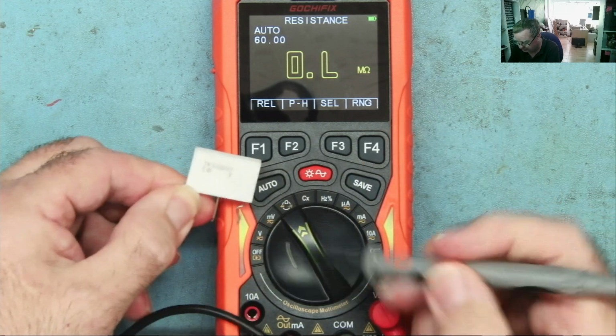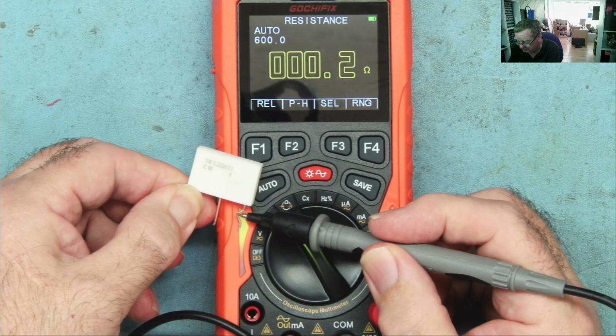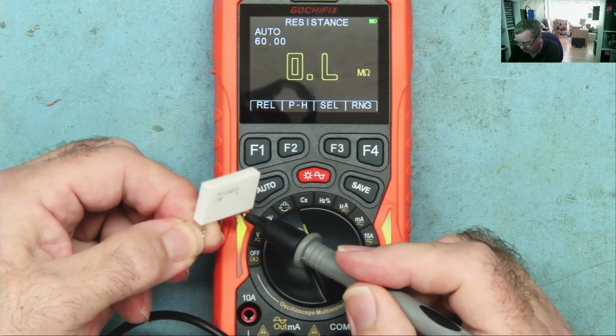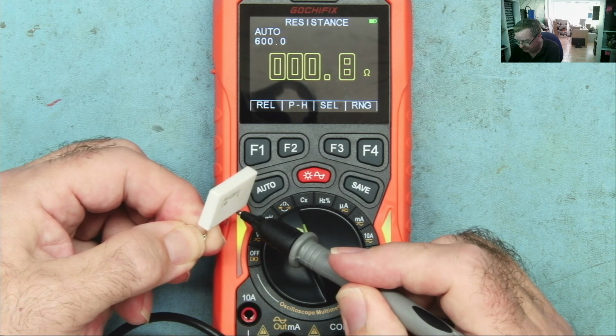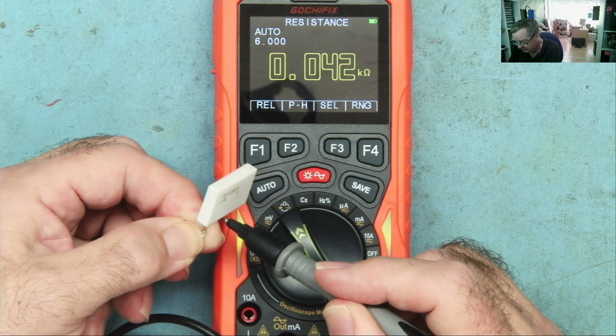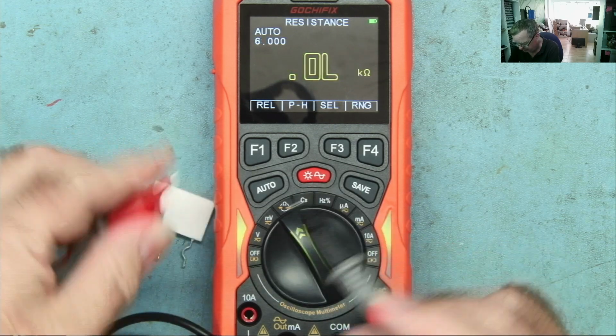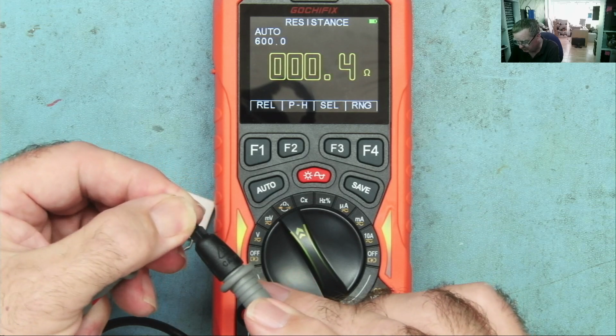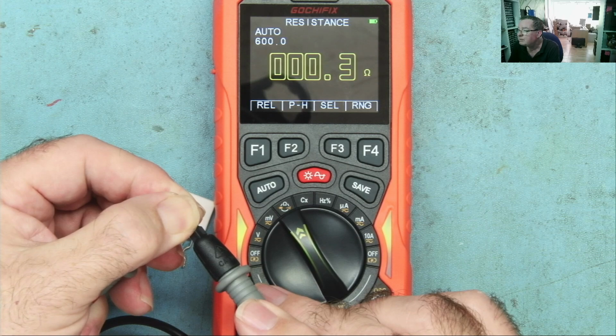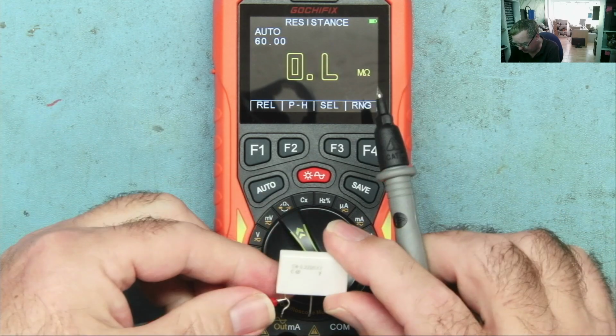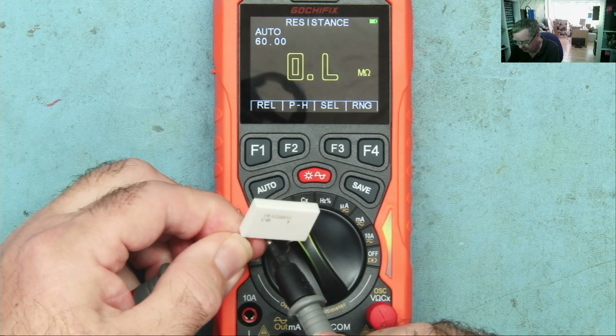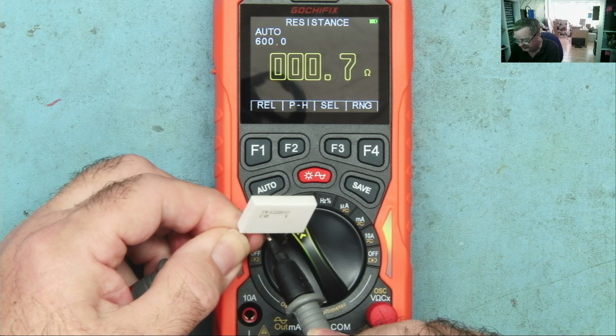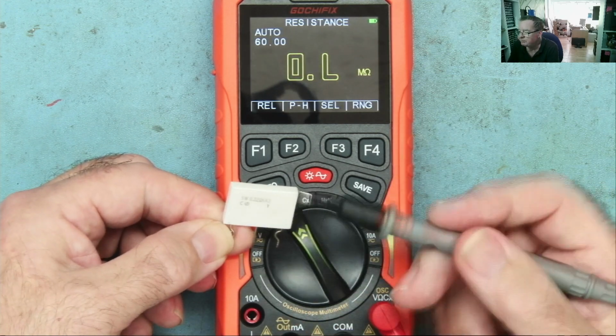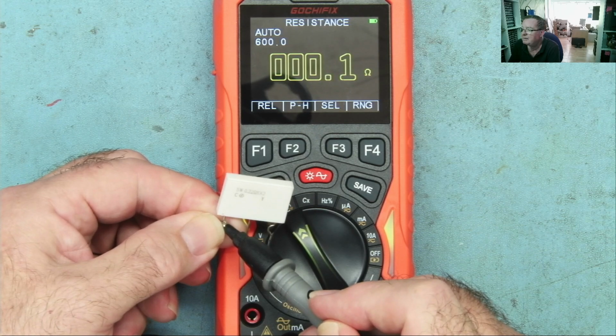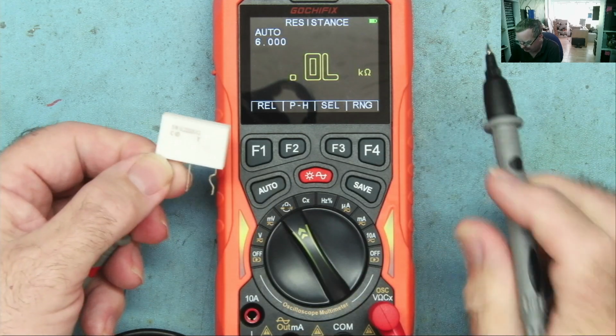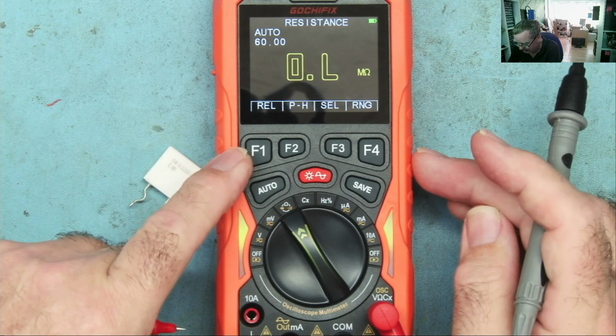We'll do it on auto first. And it's reading 0.8. 0.7. What's it reading if I short the leads? 0.3, 0.4. So this happens on my fluke meter as well, by the way. So 0.4, that's saying 0.7, so 0.6, yeah. So if we deduct the 0.4 we have there, that will actually read the correct amount. But let's go into manual range. Let's see if it works better.